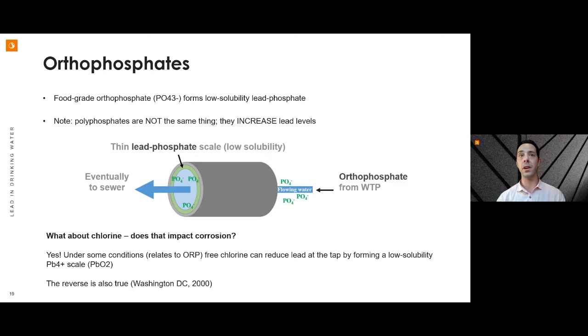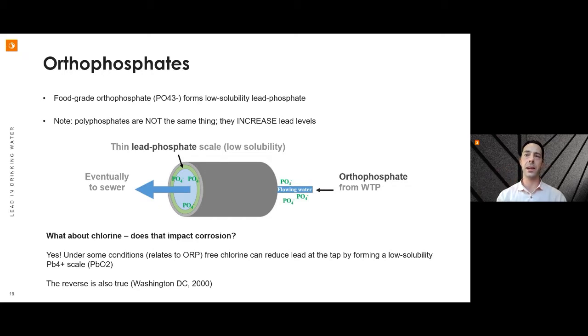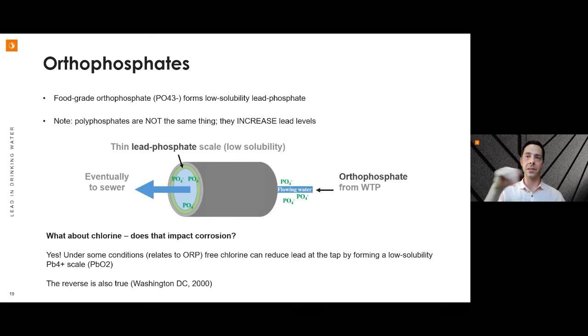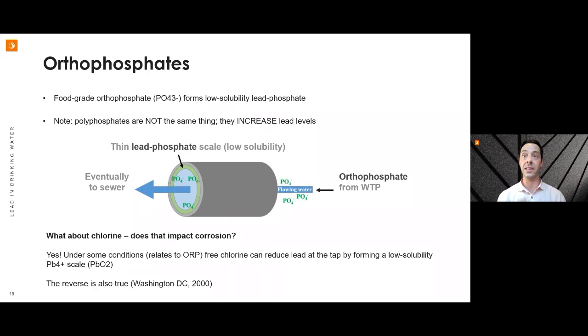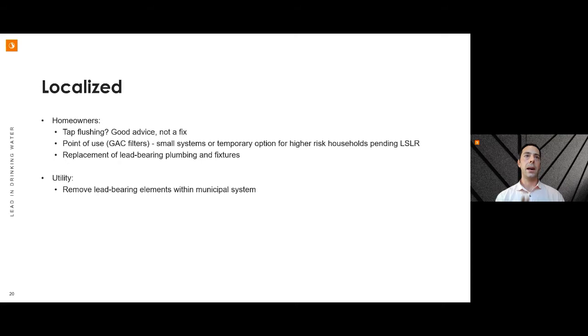Chlorine does impact corrosion in a couple of ways. It changes the oxidation-reduction potential of the water — and lead, normally a 2+ divalent cation, can be oxidised to a 4+ state when the ORP gets high enough. In that 4+ state it forms lead dioxide, which has very low solubility. Conversely, if free chlorine is lost, lead can spike upward. This was the case in Washington DC when they switched from chlorine to chloramine around 2000 — a big lead spike resulted from the change in oxidising conditions.